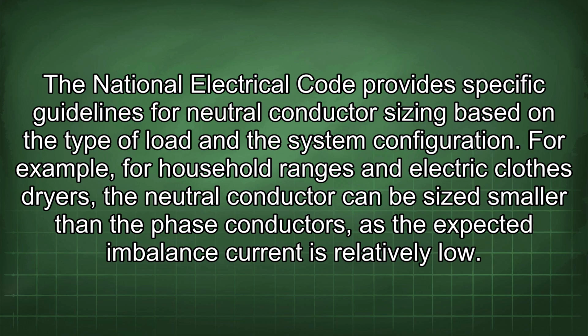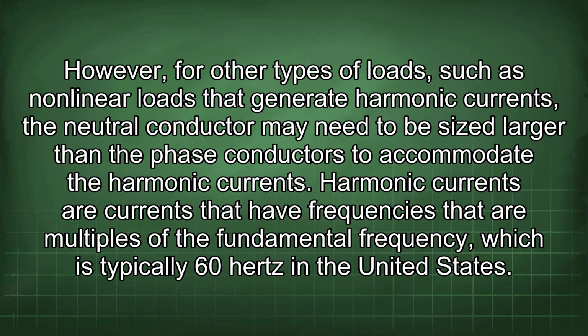For example, for household ranges and electric clothes dryers, the neutral conductor can be sized smaller than the phase conductors, as the expected imbalanced current is relatively low. However, for other types of loads, such as nonlinear loads that generate harmonic currents, the neutral conductor may need to be sized larger than the phase conductors to accommodate the harmonic currents.